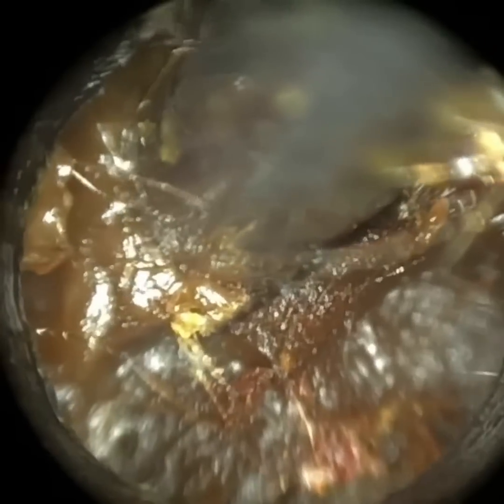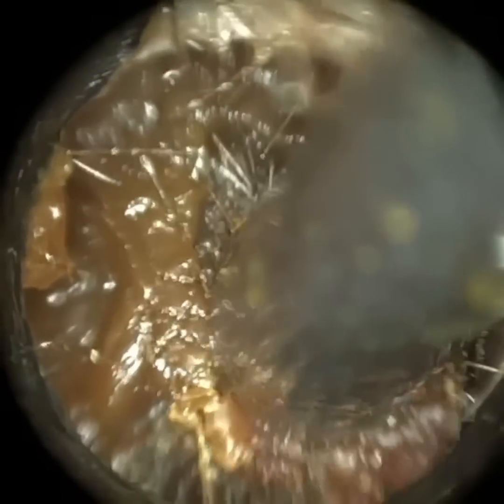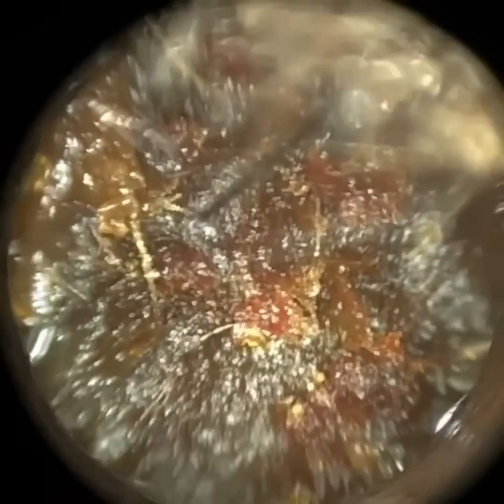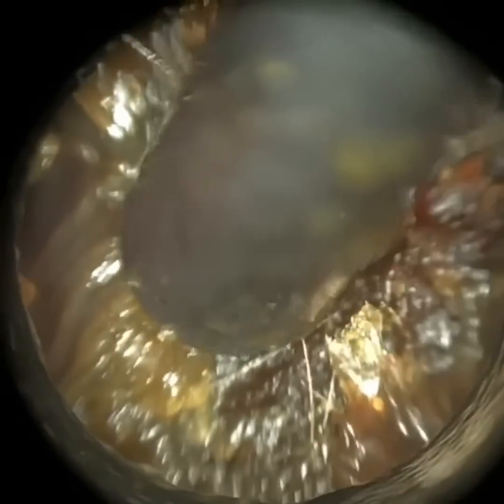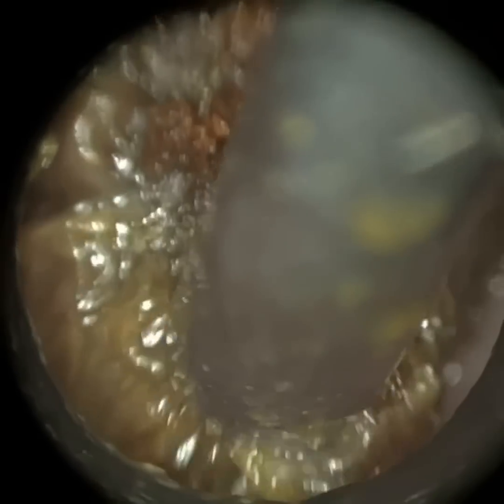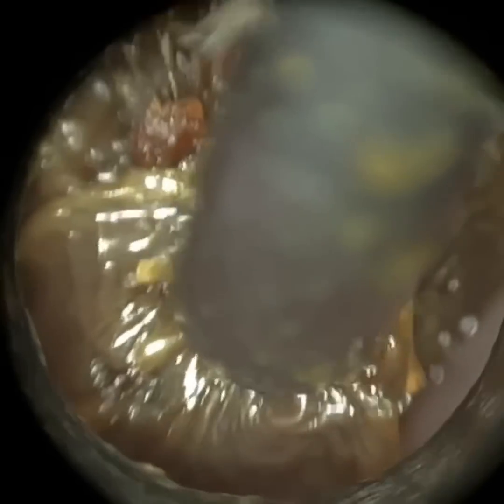The secret with this type of more lateral, soft, stodgy wax is not to over apply pressure with the suction tip, because you then just risk indenting the surface of the wax plug and blocking the suction probe. I just changed focus there, and so with that, just double tap the app, so it's got autofocus.